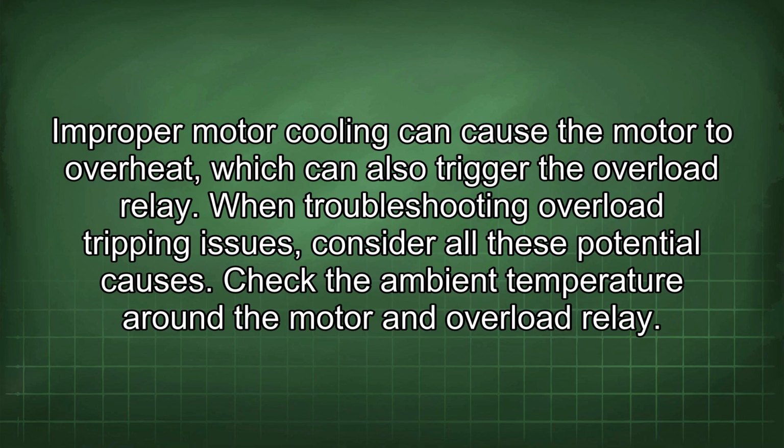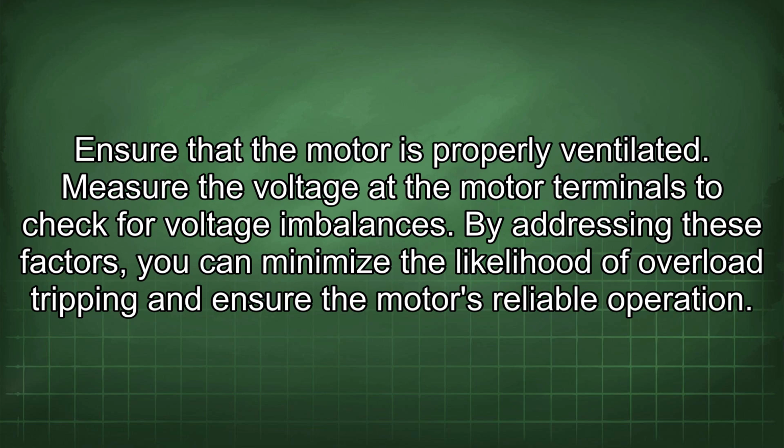When troubleshooting overload tripping issues, consider all these potential causes. Check the ambient temperature around the motor and overload relay. Ensure that the motor is properly ventilated. Measure the voltage at the motor terminals to check for voltage imbalances. By addressing these factors, you can minimize the likelihood of overload tripping and ensure the motor's reliable operation.